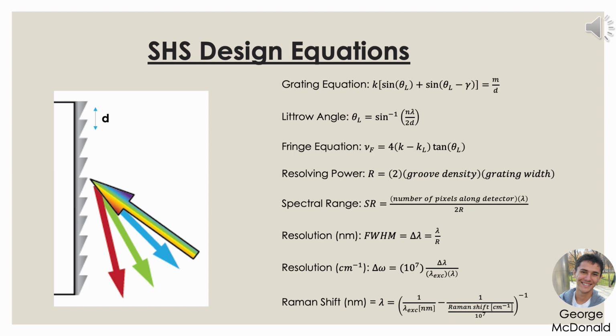The Littrow wavelength is the wavelength that produces a parallel wavefront, or in other words, where the first diffracted order is redirected back along the path of incidence. The grating must be tilted at the Littrow angle to accomplish this. Resolving power dictates resolution, and spectral range describes the wavelengths that can be imaged upon the detector.